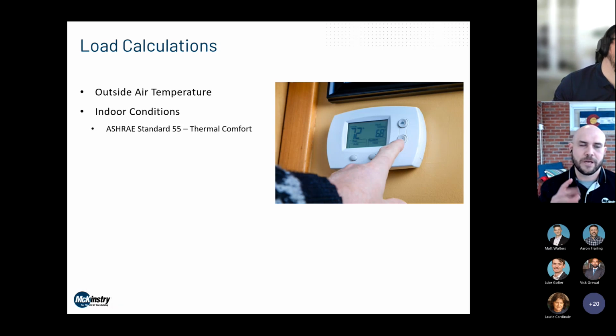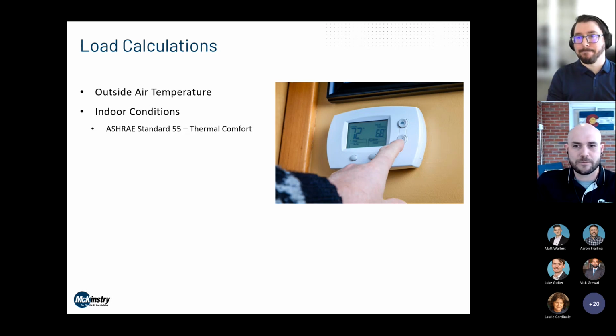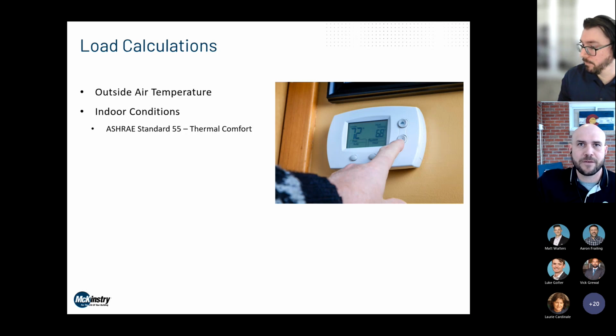So to Aaron's question, yes, I have seen a website where it's sort of projecting design conditions. All of these design conditions are calculated based on a 30-year history of what the average temperatures in every location have been like over a historical period of 30 years. That doesn't move very quickly. But if you're looking for the building to be designed for the upcoming 30 years, I have seen websites that are looking to forecast what design conditions might be for a space for a 10-year, 15, 25-year time horizon.